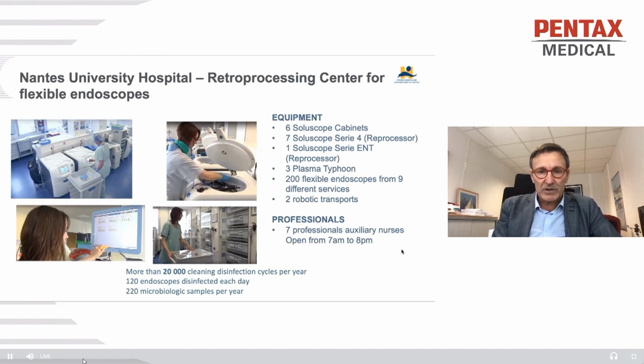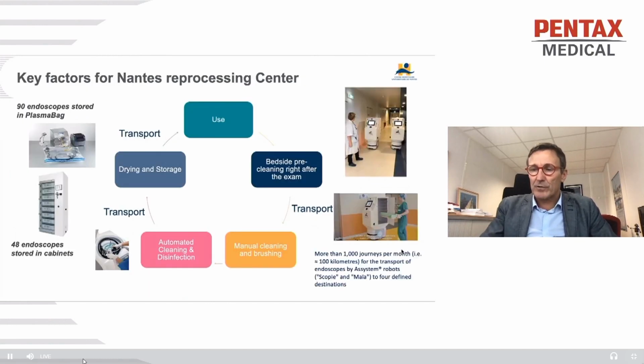Each day, more than 100 endoscopes are disinfected, and we are performing more than 200 microbiologic samples per year to assess the microbiologic contamination of our endoscope park. So what are the key factors for our retroprocessing centers from the use of endoscopes in clinical units?